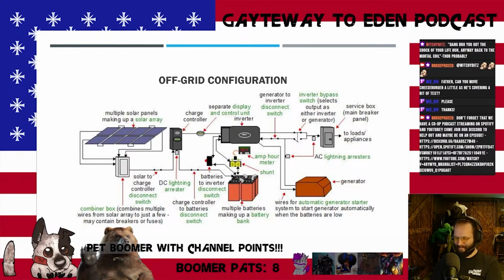If I am feeding back into the grid during a generation failure, and I have somebody downline, we'd end up with a situation like Broseph was in. Because what may be 120, 240 volts in my house, keeping my house warm, is all of a sudden 345 kV back through the power substation, back to the transmission lines.